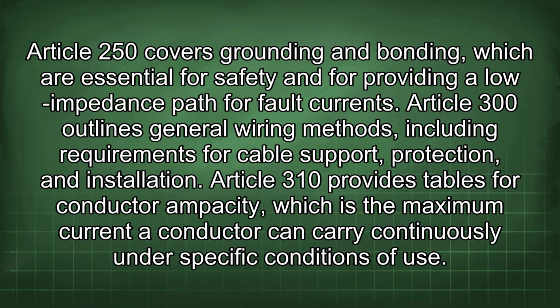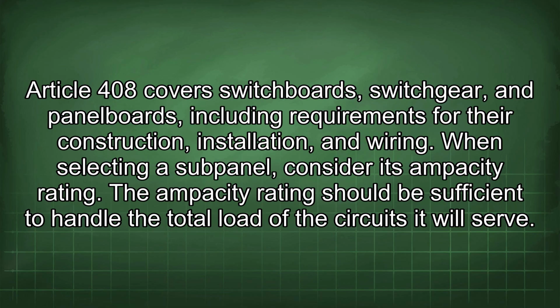Article 300 outlines general wiring methods, including requirements for cable support, protection, and installation. Article 310 provides tables for conductor ampacity, which is the maximum current a conductor can carry continuously under specific conditions of use. Article 408 covers switchboards, switchgear, and panel boards, including requirements for their construction, installation, and wiring.